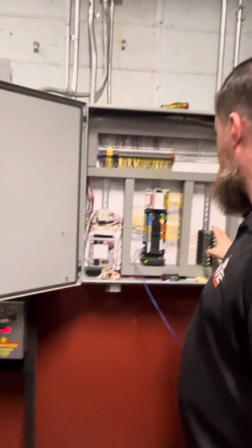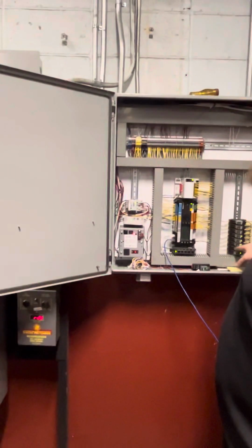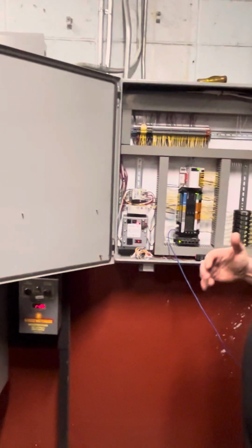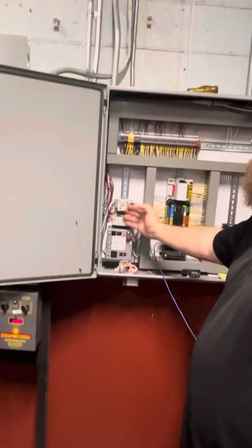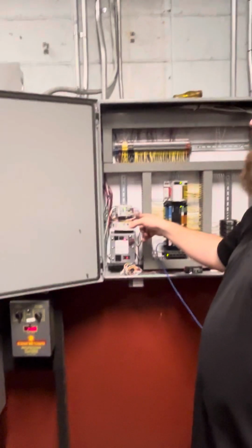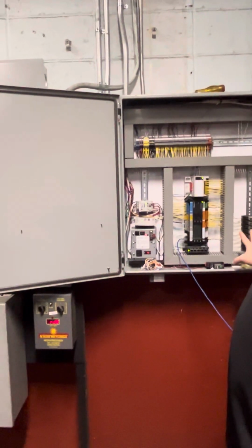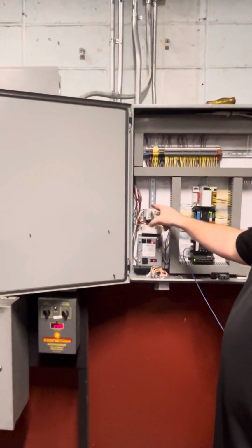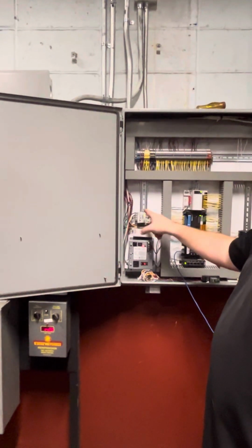There are drawings, and if you get into the drawings, I can't tell you exactly what all of these are. One is for the damper. One is the damper instance, I believe. The other three are the boiler enables. This is the biggest one here. First off, it's separated over here because this is a 120 volt coil, whereas these are 24 volt coils. This is the CO2 and glass break relay.